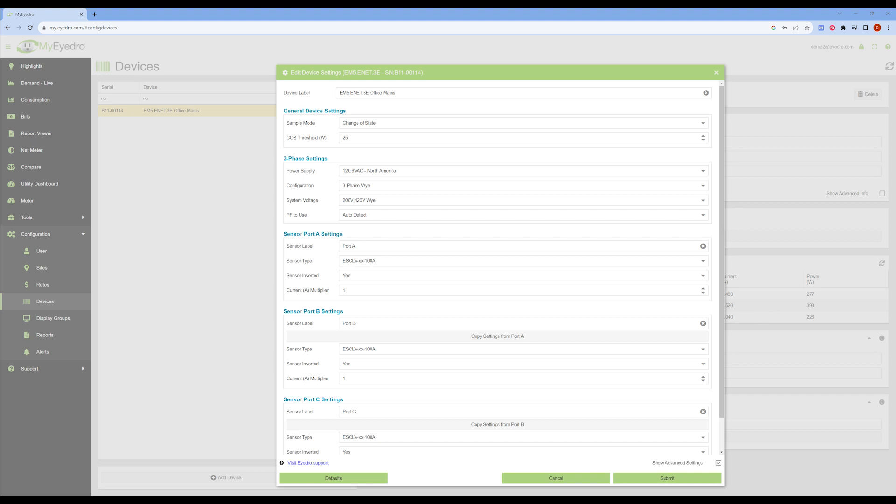In this case, each phase I'm monitoring has three parallel conductors, so I will apply a current multiplier of three to each sensor port.